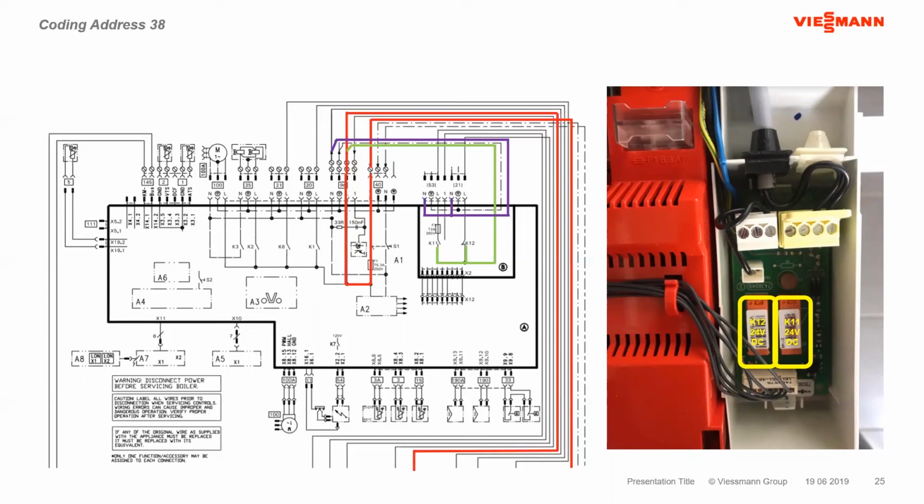We've been talking about 120 volt. These are actually switched off of a completely different type of power connection, 24 volt DC. But we are supplying 120 volt to the relay switching contact. So whatever we actually switch, we're still going to measure 120 volt as a result of that coil being energized from between the K11 and the K12.